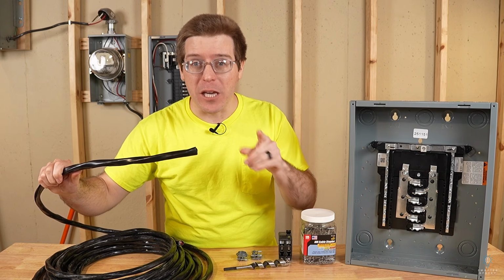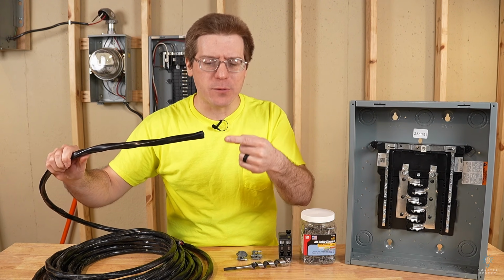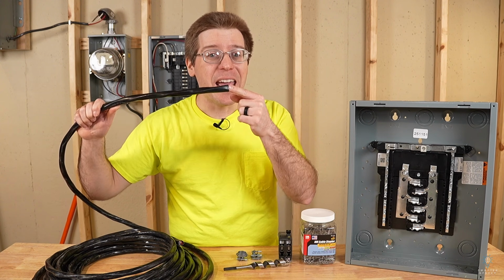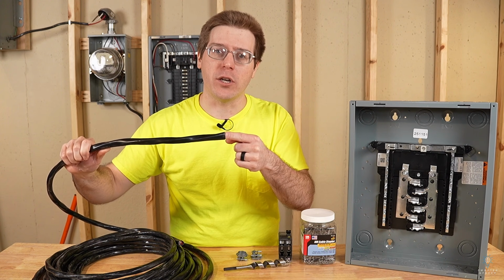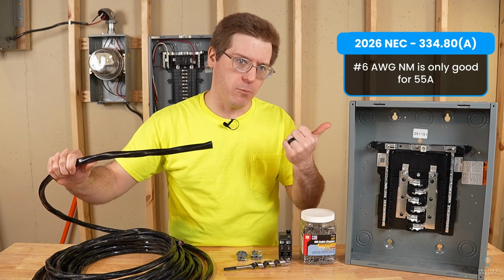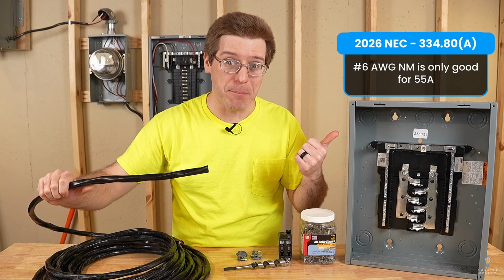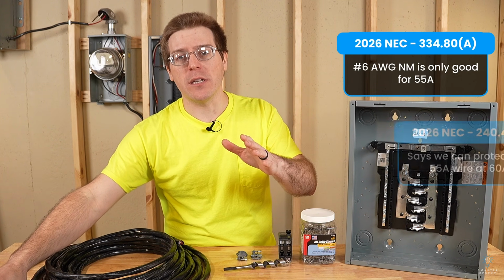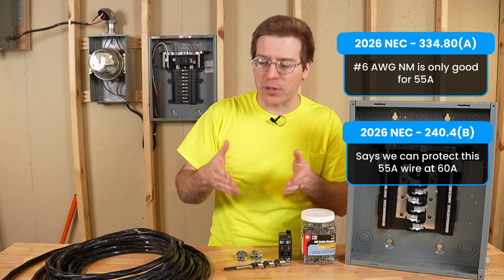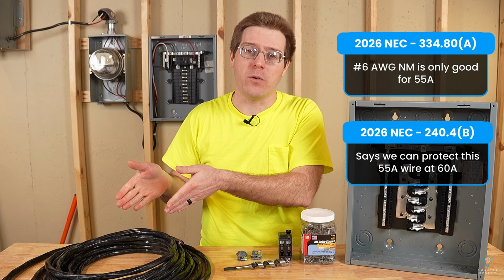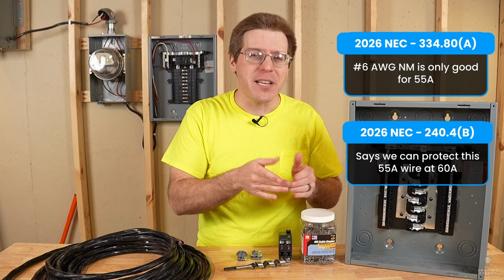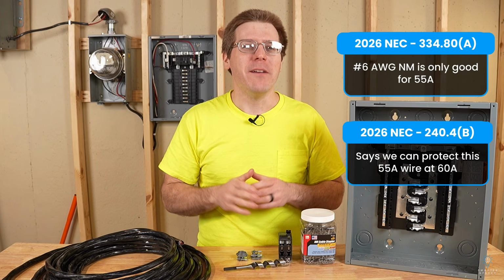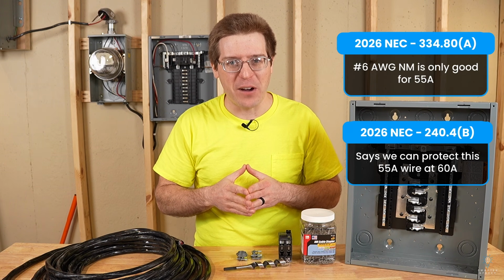Now, for those of you keeping score at home, you might realize, well, wait a minute, 6 gauge NM wire is actually only good for 55 amps, and we're going to be running this on a 60 amp panel, right? There is an exception in the code that allows us to protect that 55 amp rated wire at 60 amps, so long as we pinky swear that we're not going to exceed that 55 amps.